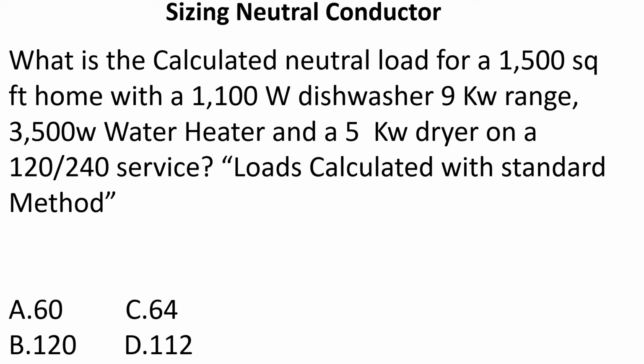What is the calculated neutral load for a 1,500 square foot home with an 1,100 watt dishwasher, a 9 kW range, a 3,500 watt water heater, and a 5 kW dryer on a 120/240 volt service? I'm putting in here that the loads are calculated using the standard method. Okay, so first we're going to figure out our VAs per square foot. We've learned this already. This is our basic load calculation.